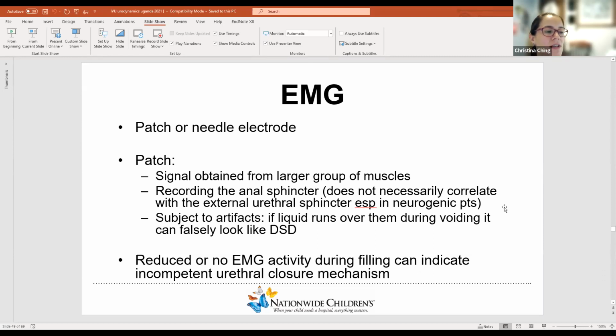Patch is a less invasive way of looking at EMG activity. They literally put patches on the perineum. There are some problems with it in that it obtains information from a larger group of muscles, because it's not specifically in the pelvic floor or in the urinary sphincter. So it can record the anal sphincter, which doesn't always correlate with what's happening with the external urethral sphincter. And it can be subject to artifact, because if they start leaking or if they're voiding and the liquid runs over the patch, it can really, I'll show you an example of that.